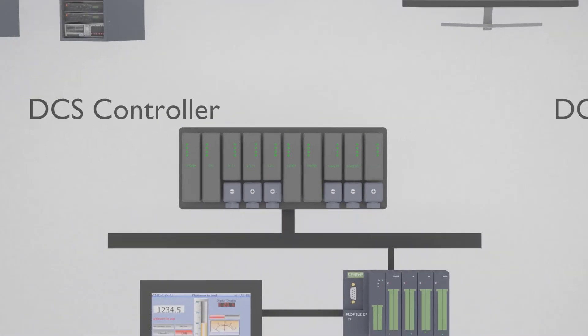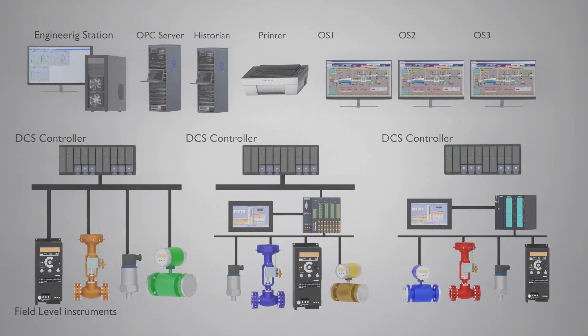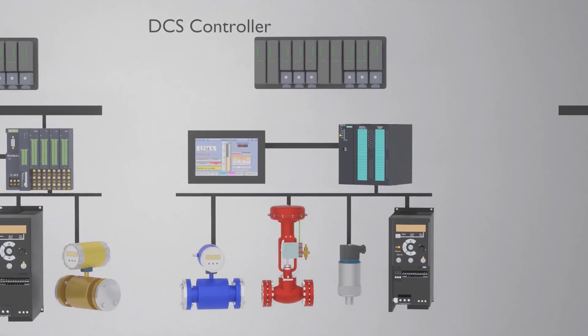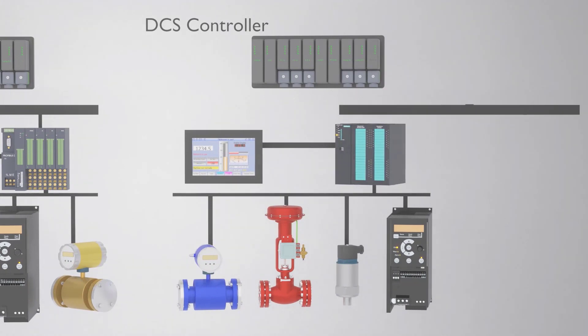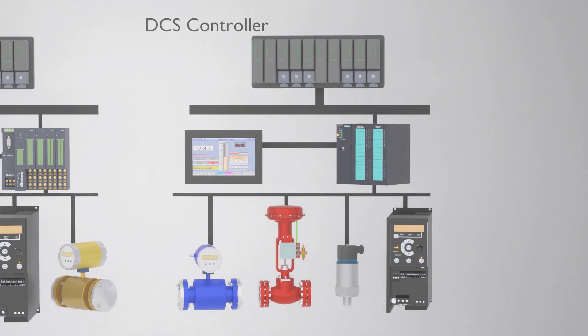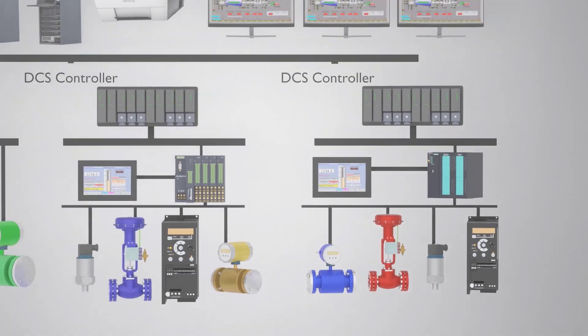Field instruments are connected to the control station in each area. An important question is: can a PLC be part of a DCS system? In some scenarios, you might have a PLC linked with a DCS, sharing data with your DCS network. As you can see here, a PLC is connected to field instruments and to a local HMI, but that PLC is then sharing data with the DCS controller. We can also connect an existing PLC in an area to the DCS network.